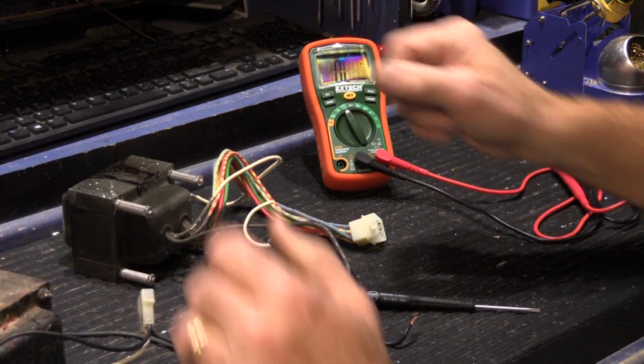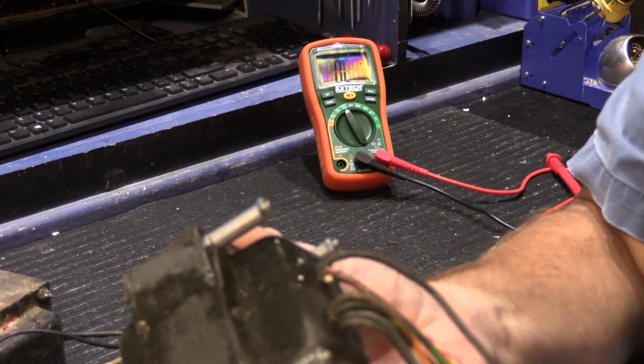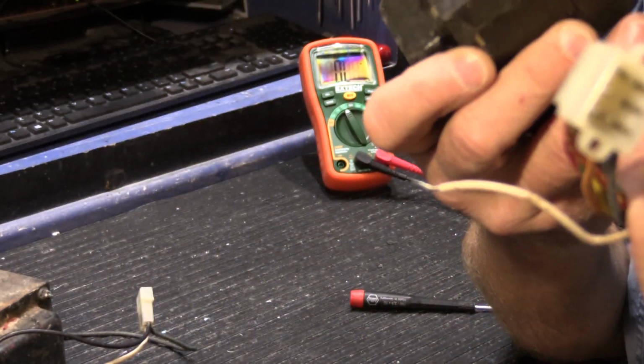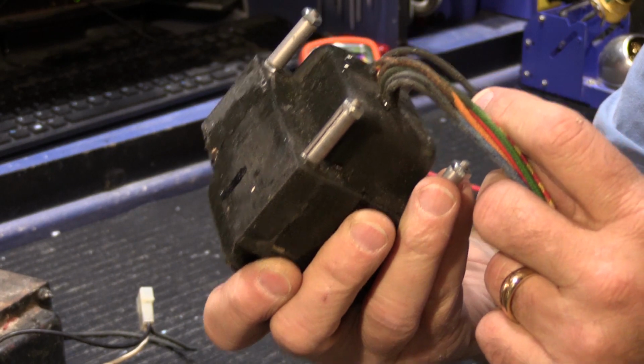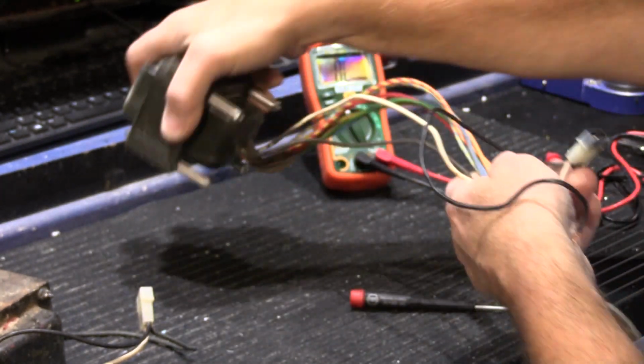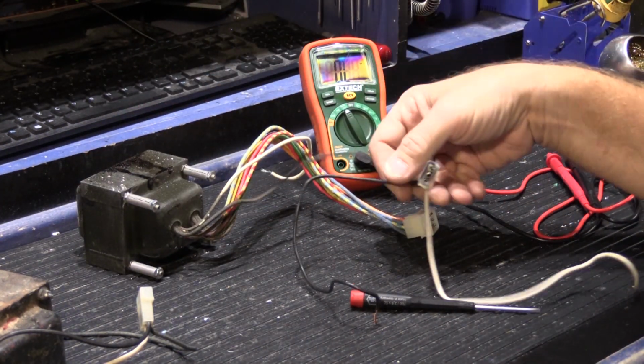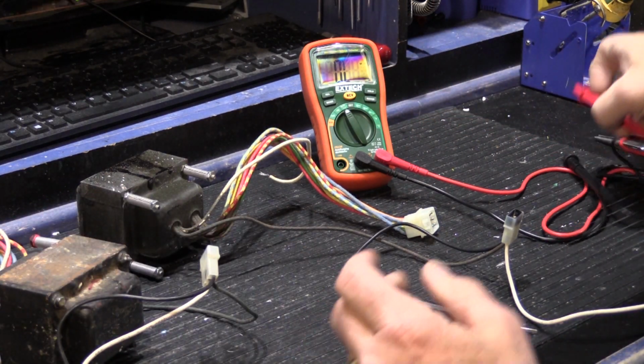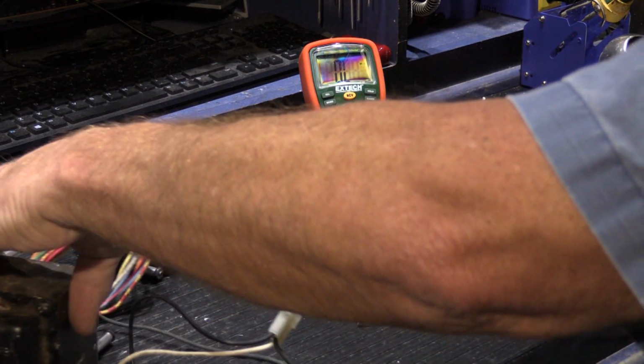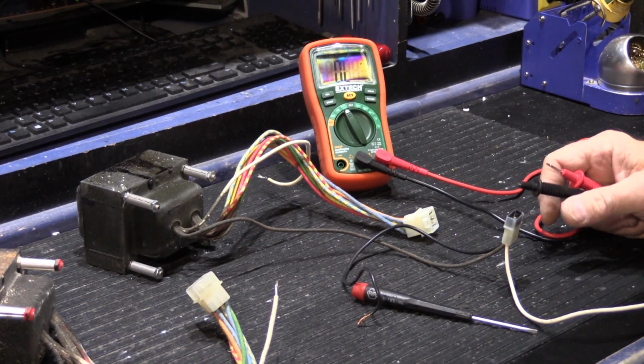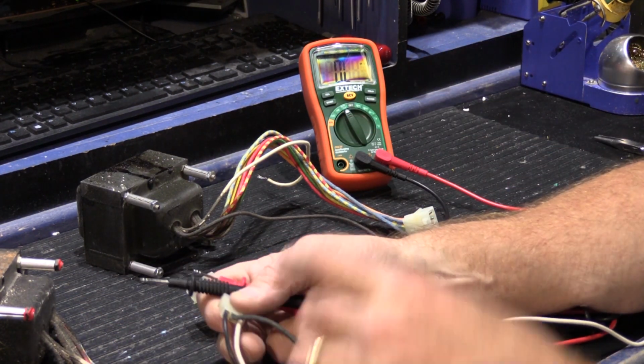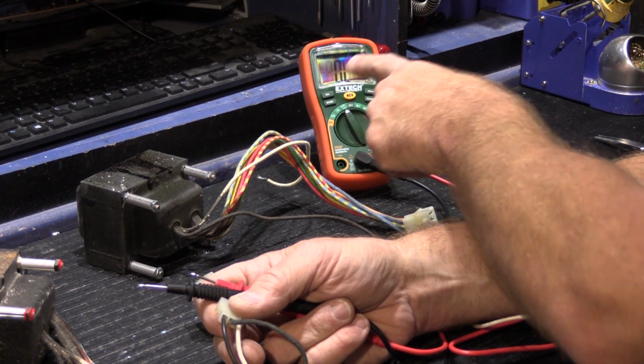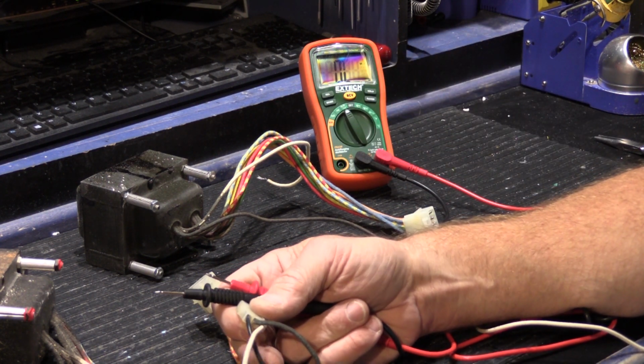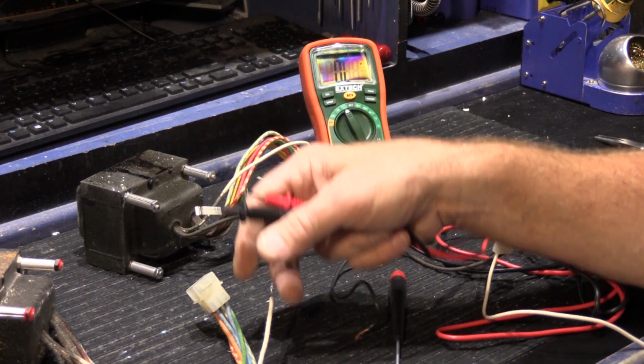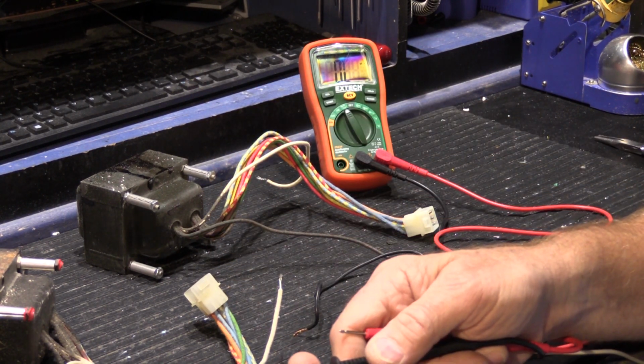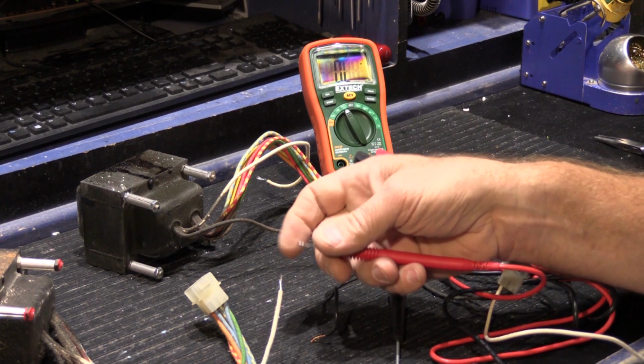So the first indication that it could be bad is you've got to give it the sniff test. It does have that sort of acrid burnt sugar smell you get when windings in the transformer go bad. Next, we can measure the resistance of the primary coil with a multimeter, which you can see right here. Sorry about the reflection, that's the lights above the workbench. If we go ahead and hook this up with our multimeter, this is the good one.